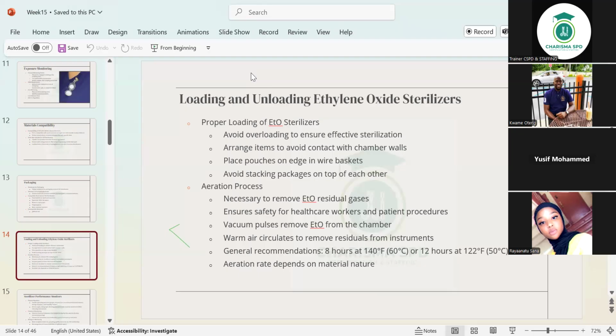And this is just what I wanted to explain to you. It doesn't mean cold sterilization. It says low temperature, and the low here is under 140 degrees Fahrenheit. It's recommended that aeration should take 8 hours at 140 degrees Fahrenheit. And that is not cold, but it's low compared to steam.